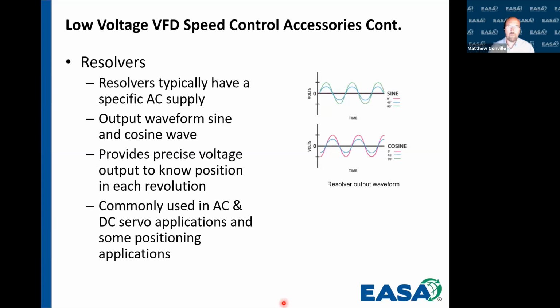The second type of speed control is actually called a resolver. And resolvers, they're a little bit different. So we said in DC, they have, or in incremental, they have a DC power supply. Resolvers have a very specific AC power supply that they use. And the output waveform looks like a cosine and a sine wave. So it has a sine wave and a cosine wave. And what it's going to do is it's going to provide a very precise voltage at the known position in each revolution. And that's what the I/O card is looking for. So it has to be an analog card so that it can sense that voltage.